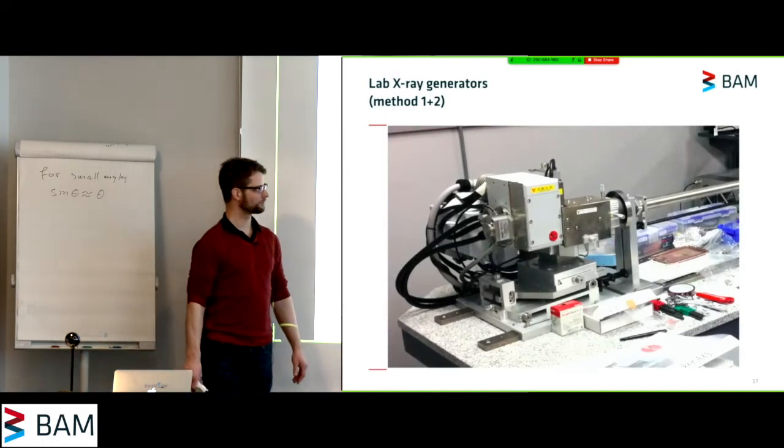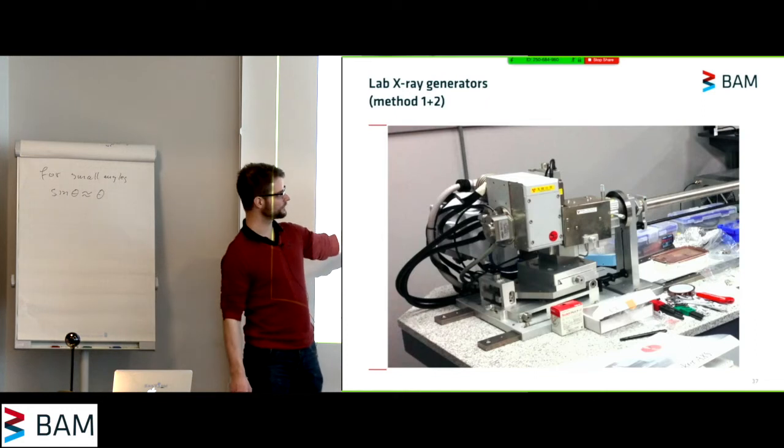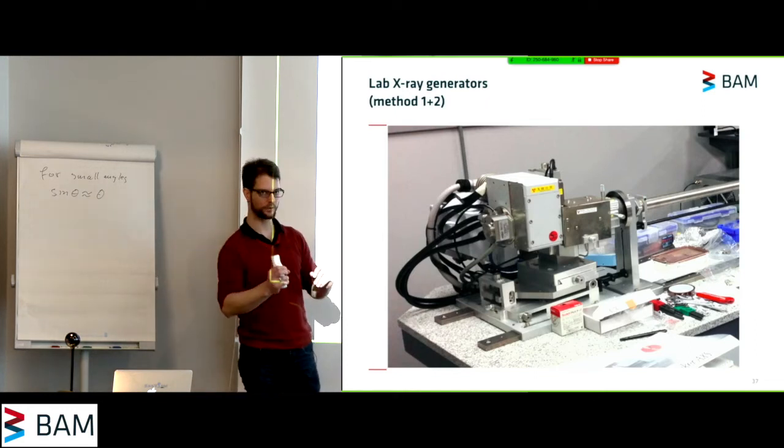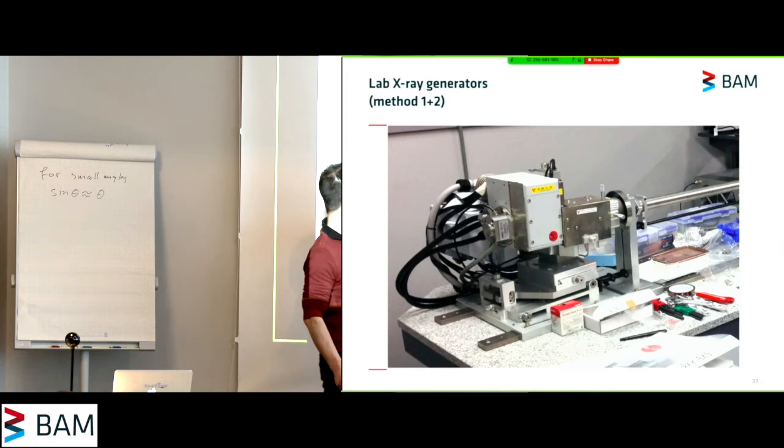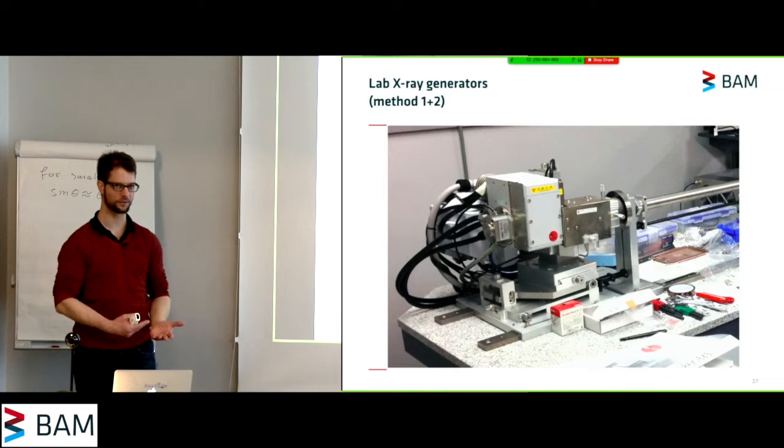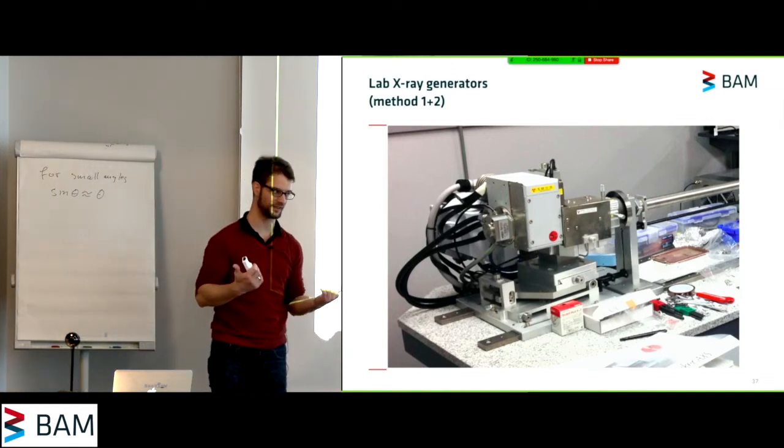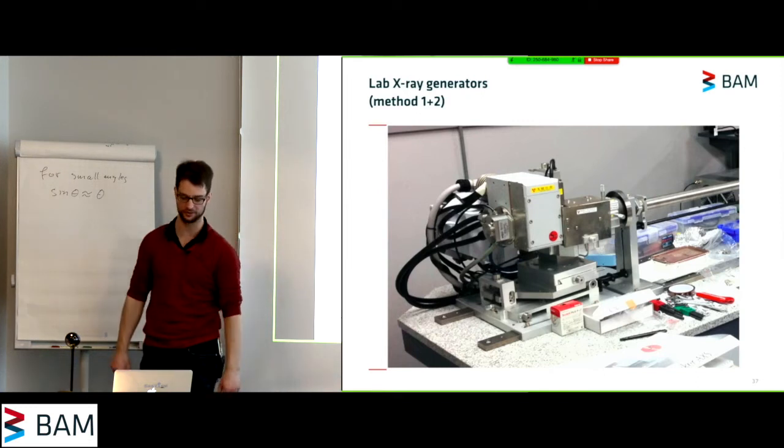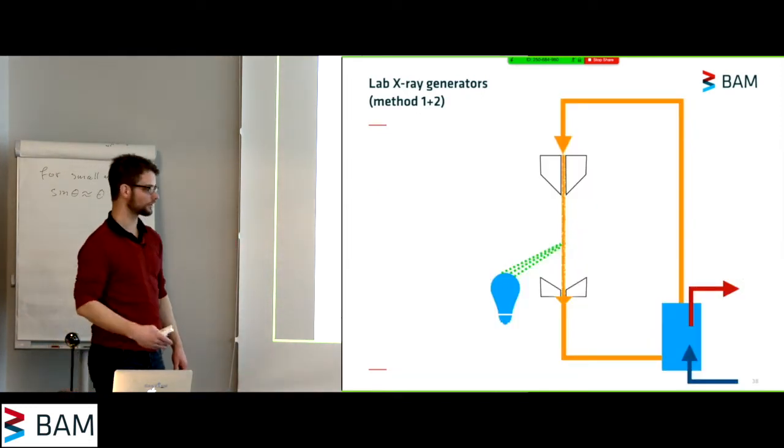One of these rotating anode generators is pictured here. This is a Bruker example. You can change between point focus and line focus by rotating, by putting your whole target assembly either vertically or horizontally. So on these rotating anode generators, you usually only have two exits, which are either point exits or line exits, depending on how your target is oriented.